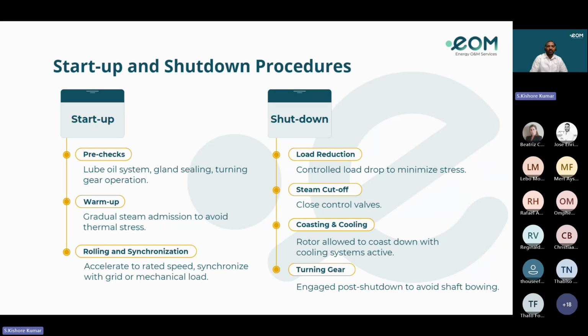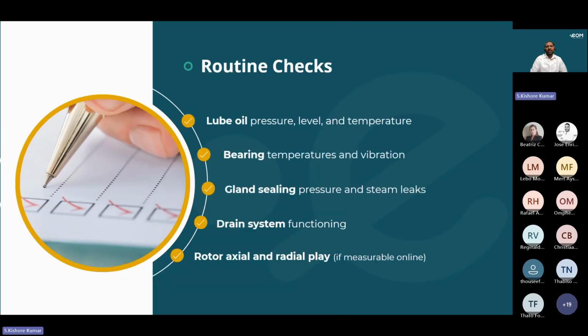If we stop the turning gear early without cooling down, the rotor will be deformed or bowed, and that will cause damage to the rotor. So always follow the O&M preferences on how much time we have to wait to totally stop the turbine and the turning gear. The routine checks must always be carried out without exception, as they provide critical insight into the health and operational status of the turbines.